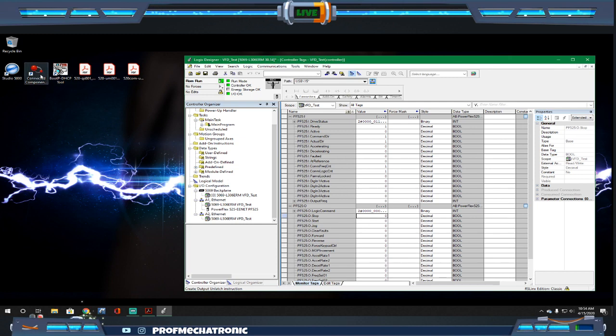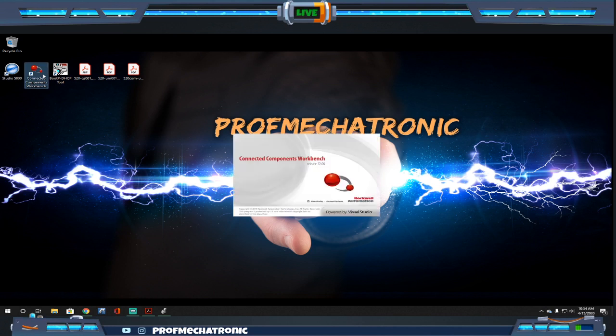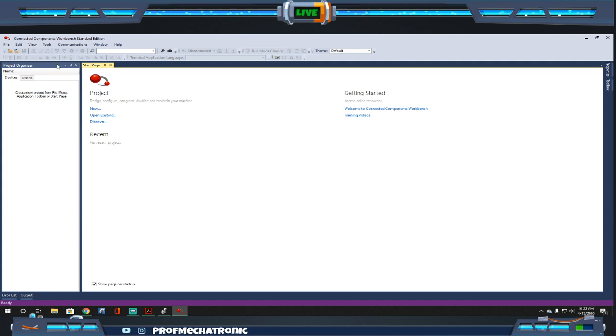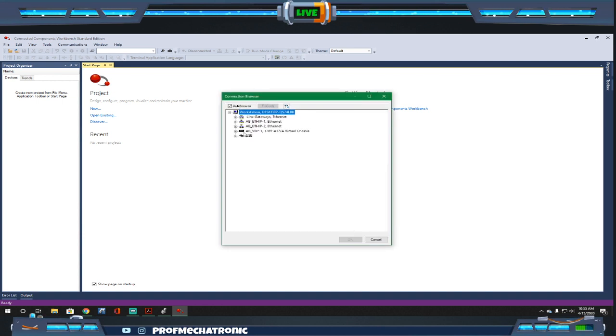One other thing we can talk about, while I see if there's any questions coming up, is Connected Components Workbench. Connected Components Workbench is a cool software that allows you to do a lot of device configurations externally. You're going to see that when I go to Connected Components Workbench, it's going to look very, very similar to what we've had before. So I'm going to go to Discover because I'm going to be looking for a device on the network. When I go to Discover, it's going to show up a connection browser for me. I'm going to go to Ethernet IP because I know that's where my device is, find my PowerFlex drive, and hit OK.